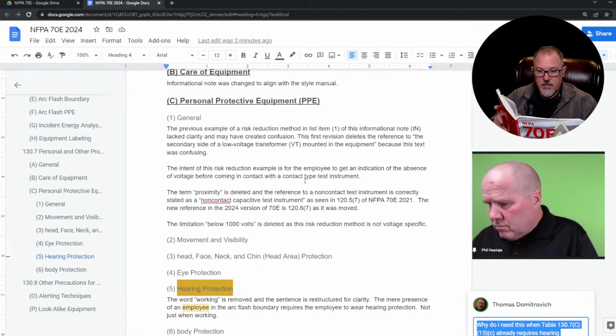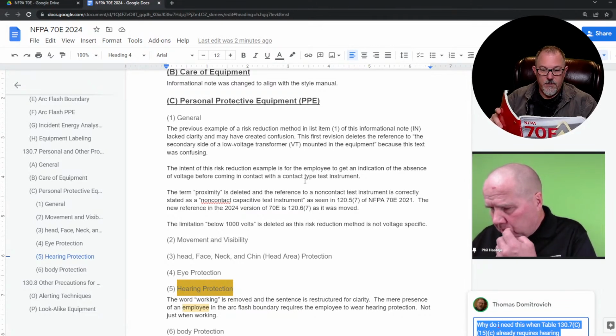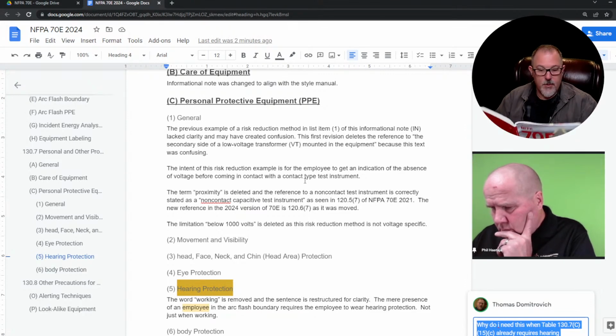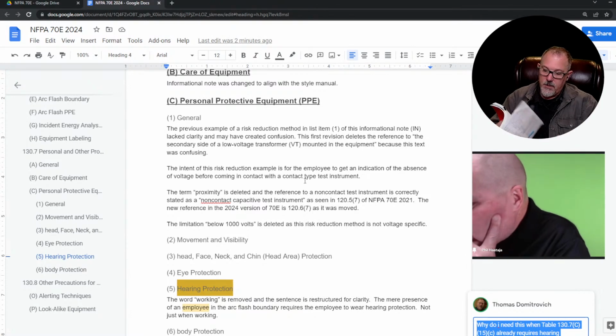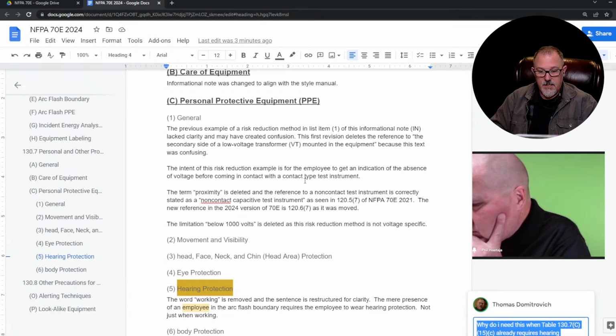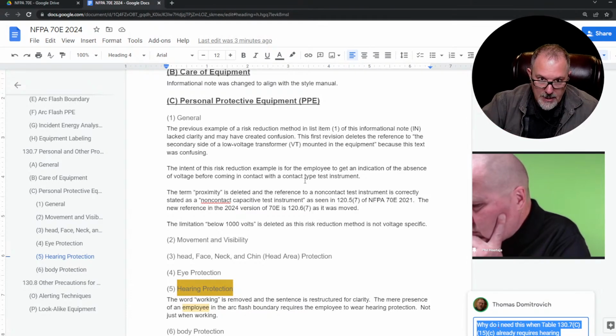Mm-hmm. Eye protection says shall wear protective equipment for the eyes whenever there is danger of injury from electrical arcs, flashes, or flying objects. So that's general. And it says hearing, employees shall wear hearing protection whenever working within the arc flash boundary. So 5 is not appropriate because 5 is already covered in 130.7C15C. That's where you're determining your PPE. Now, if they said you need to have hearing protection anytime you're working in areas with loud noises, etc.